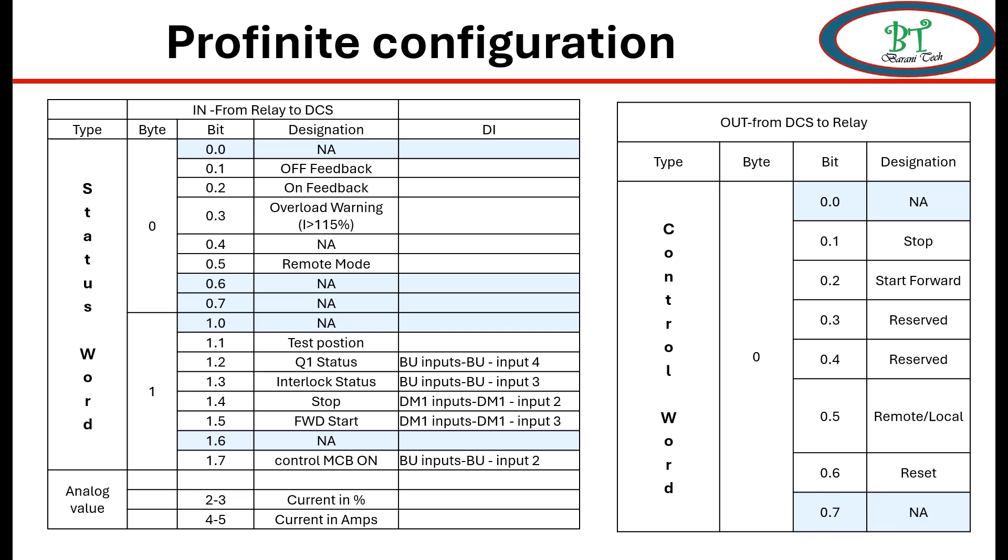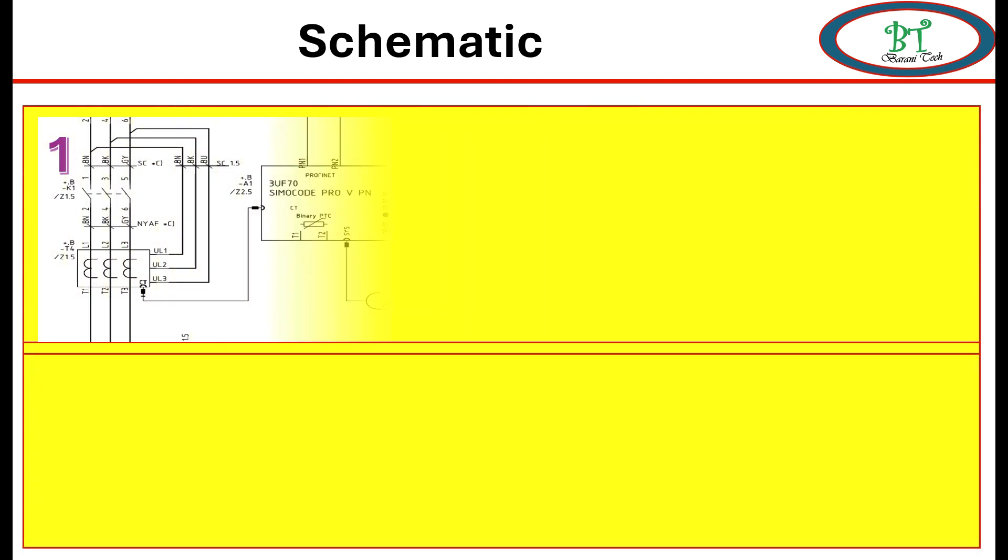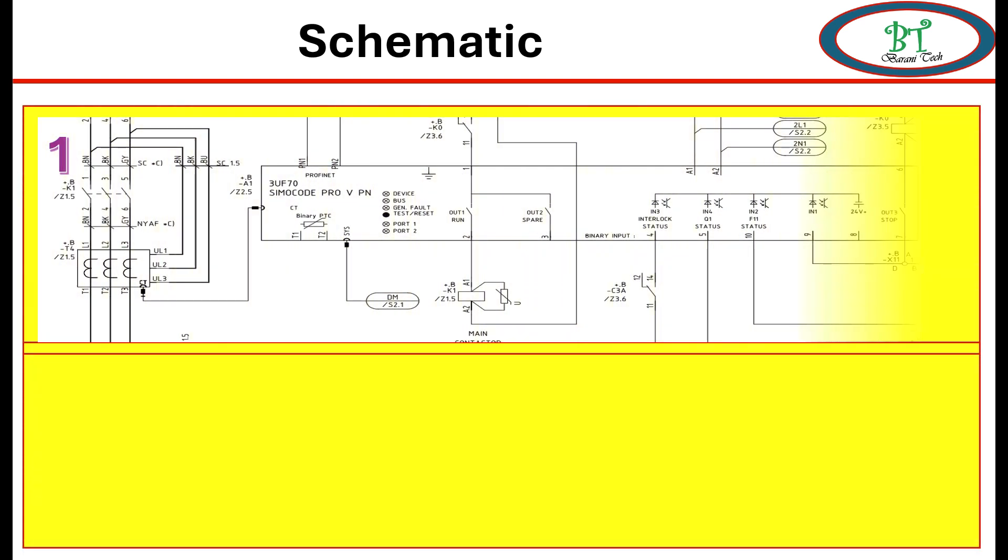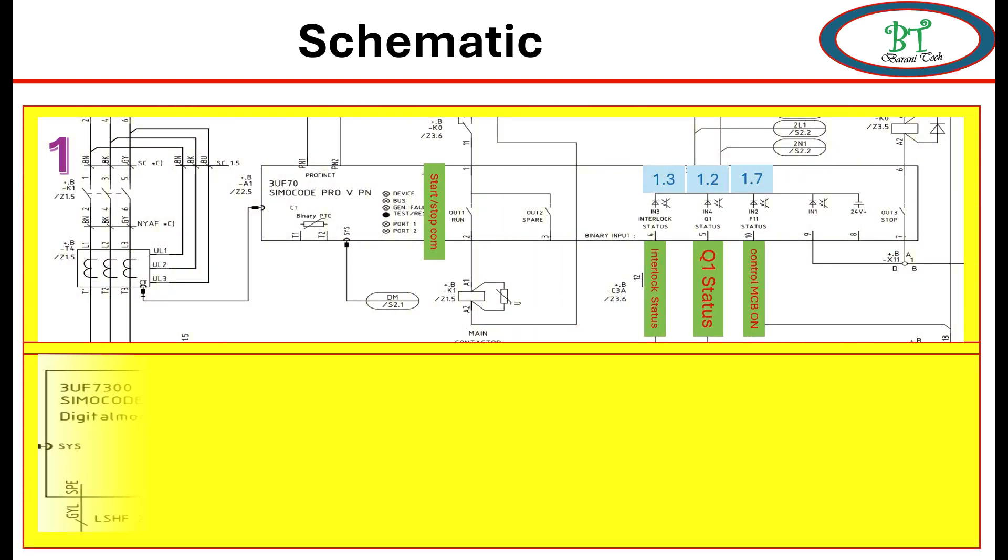Same way, for DCS to relay, command needs to configure correspondingly receive bit. Example like 0.0 none, 0.1 stop, 0.2 start forward like this. So by having this signal list, we are going to see how to do configuration on relay through software.